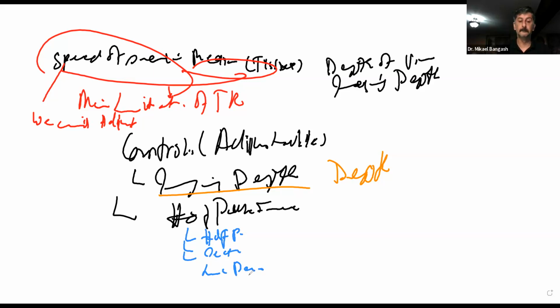There are functions on your system where you can increase or change the number of focal points, change the sector shape and size, and increase or decrease the line density accordingly. But these were mainly the two major controls that determine the temporal resolution.